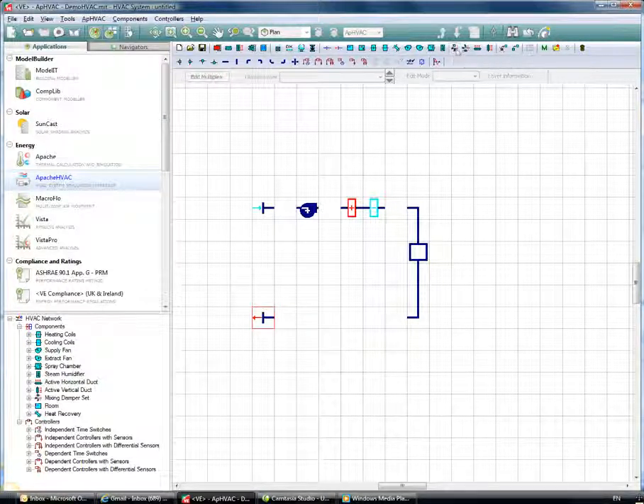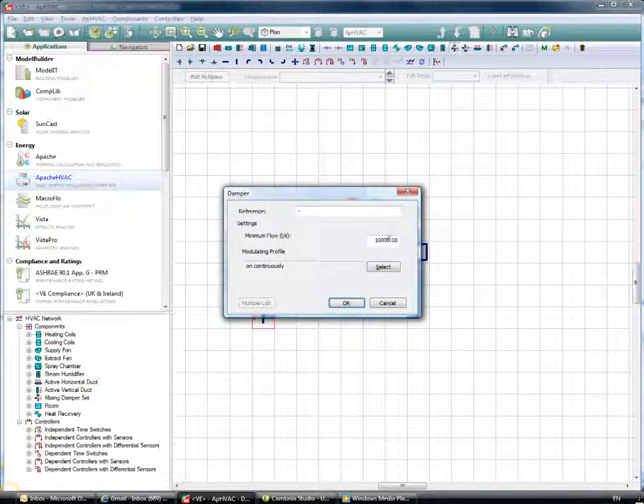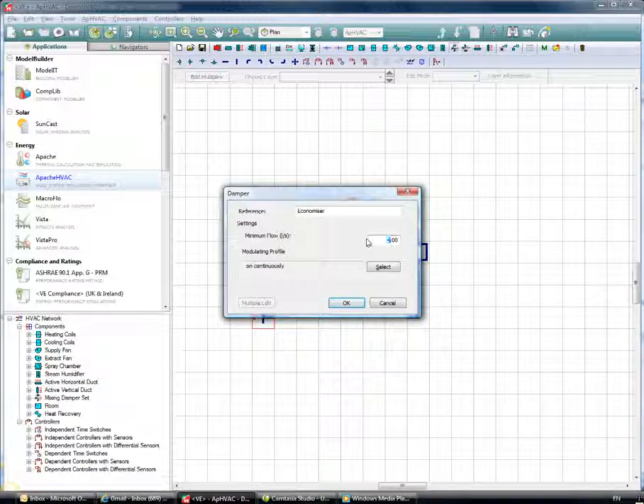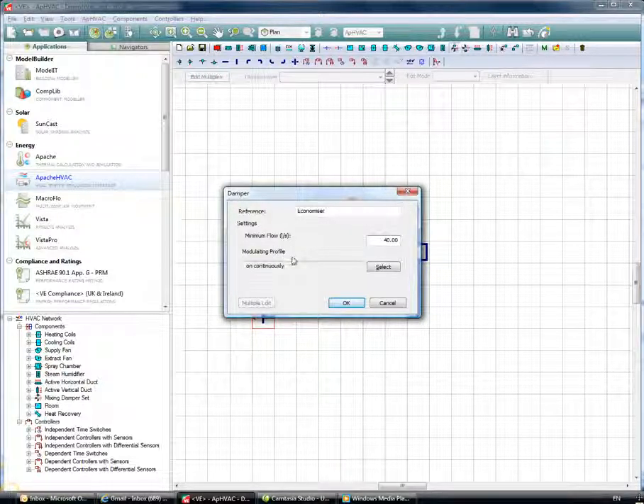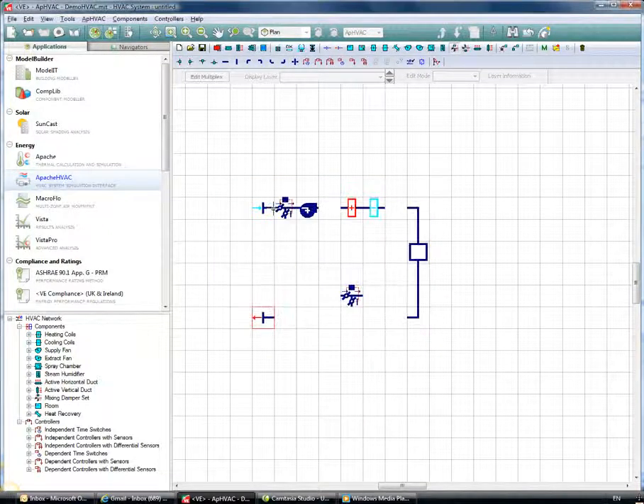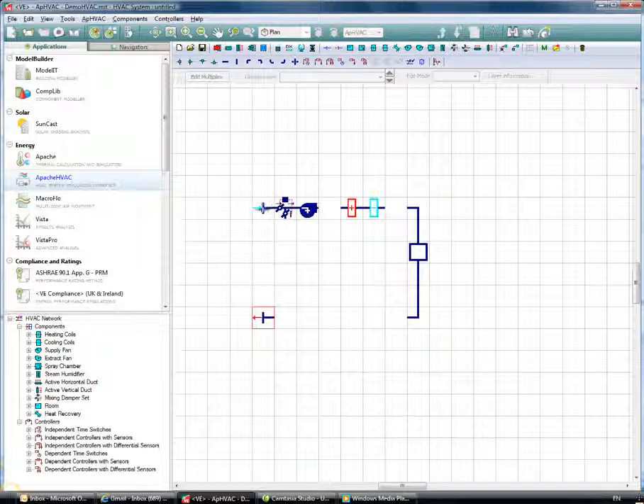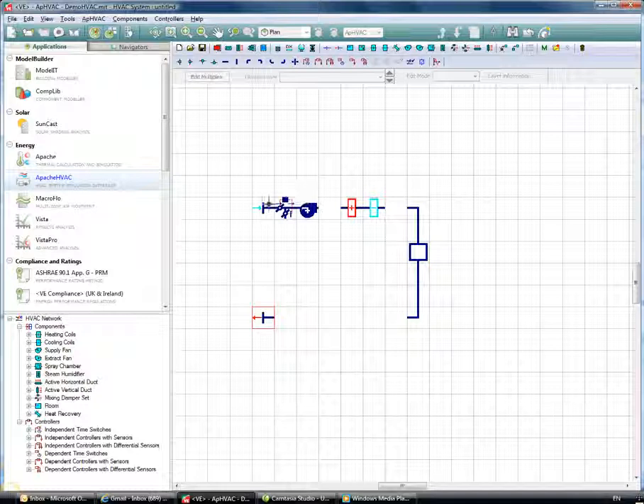Next I'll include an outside air economizer by choosing a mixing damper set. I'll call it 'Economizer' and set a minimum flow rate of 40 liters per second. This is to meet the fresh air requirements in the space — the minimum flow setting means the air passing to the left branch will never drop below 40 liters per second, which is the outside air. So the minimum outside air flow rate is never allowed to drop below 40 liters per second.